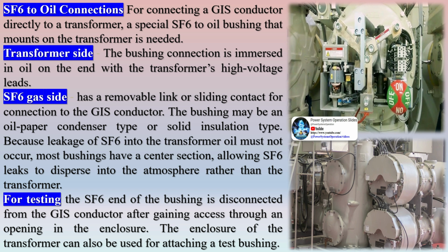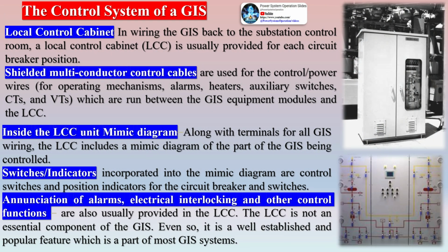SF6-to-oil connections: for connecting a GIS conductor directly to a transformer, a special SF6-to-oil bushing that mounts on the transformer is needed. Transformer side: the bushing connection is immersed in oil on the end with the transformer's high voltage leads. The SF6 gas side has a removable link or sliding contact for connection to the GIS conductor. The bushing may be an oil paper condenser type or solid insulation type. Because leakage of SF6 into the transformer oil must not occur, most bushings have a center section, allowing SF6 leaks to disperse into the atmosphere rather than the transformer. For testing, the SF6 end of the bushing is disconnected from the GIS conductor after gaining access through an opening in the enclosure. The enclosure of the transformer can also be used for attaching a test bushing.